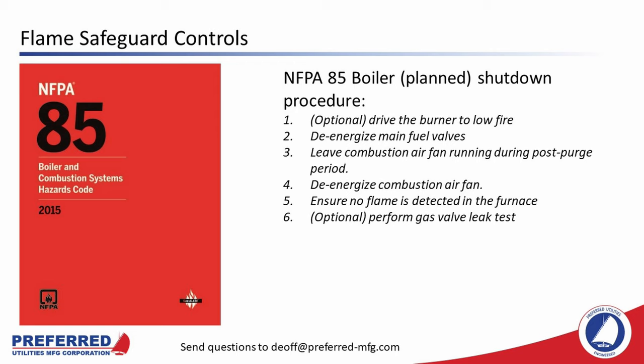A planned boiler shutdown can be performed if the boiler water level goes below the first low-water cutout switch, or if the steam pressure goes above the first operating steam pressure or hot-water temperature switch. The planned shutdown procedure as dictated by NFPA 85: first — optionally — drive the burner to low fire. Then the flame safeguard controller will de-energize the main fuel valves and leave the combustion air fan running for usually 25 seconds for post-purge — though on some controllers the post-purge timing is adjustable. Then it de-energizes the combustion air fan, ensures no flame is detected, and may perform a gas valve leak test. This optional low-fire step is called Assured Low Fire Cutoff — it reduces thermal shock on the boiler.